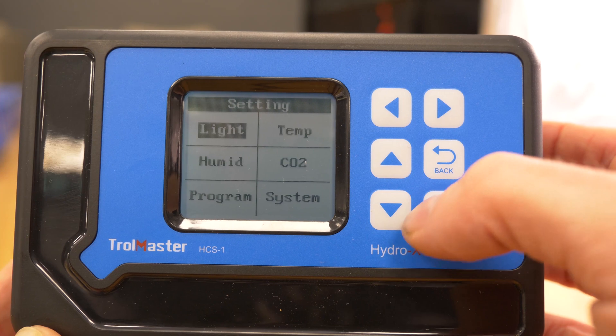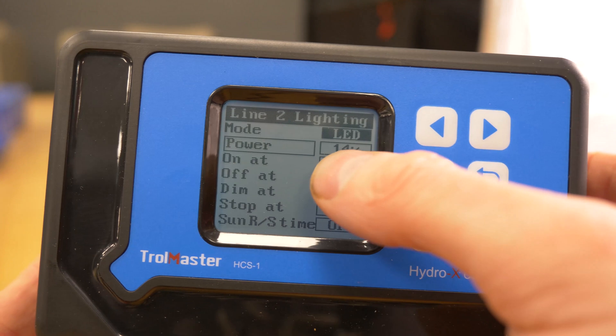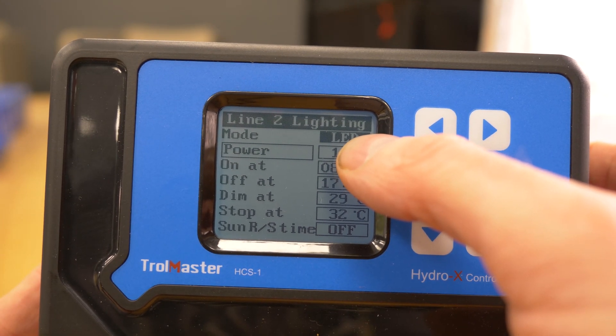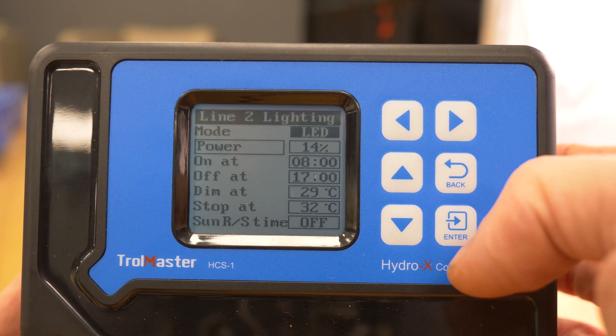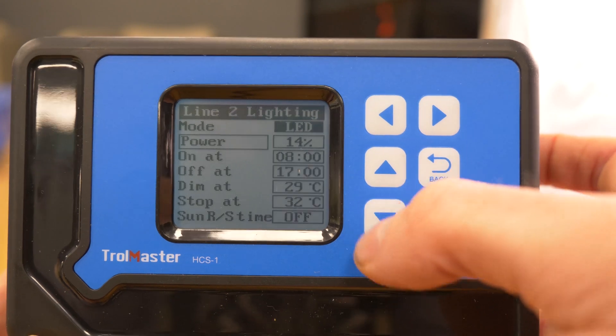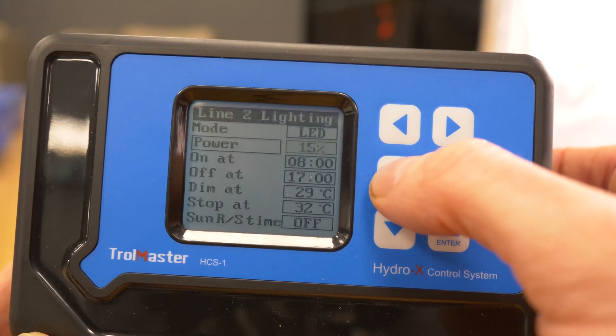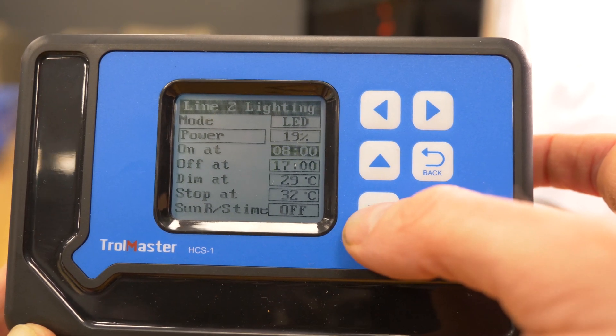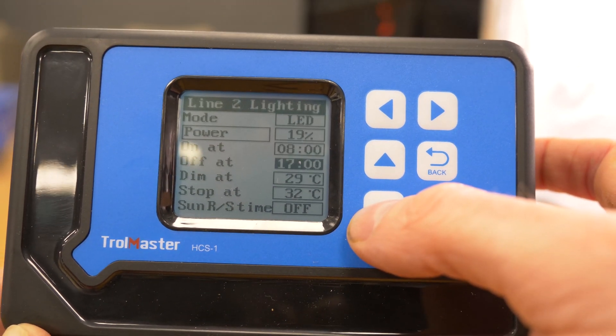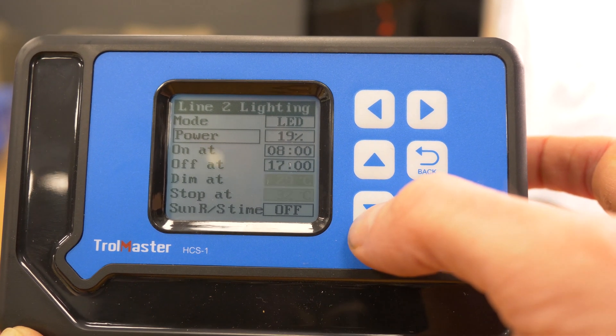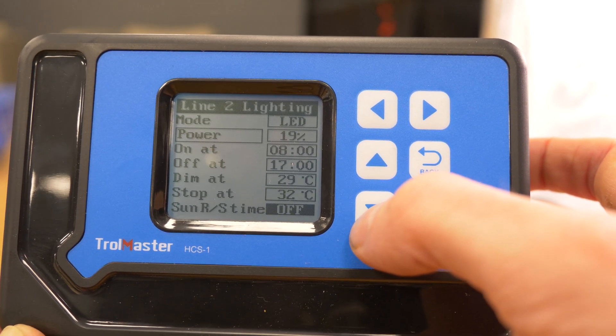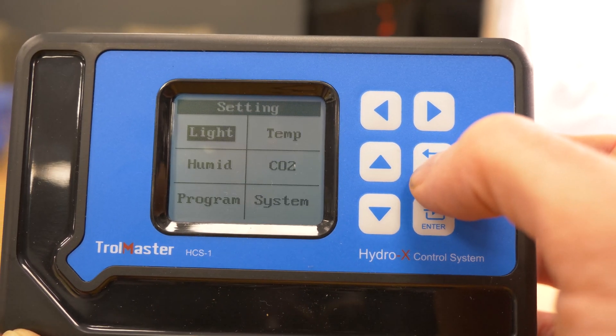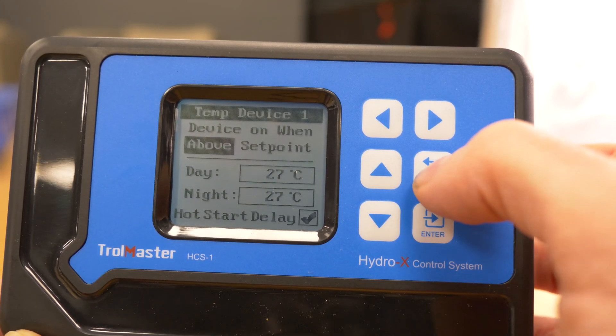With light, power is currently set for LED or HID. Power is set for 14%, that's the target on level so we don't get too much glare. To change any of the settings go to the particular box, enter and just increase or decrease. Then we have the on off time and you have the additional functions which if you're getting over temperature you have an additional function to dim the lights and to stop them or switch them off if it gets to very high temperature. You also set sunrise and sunset.